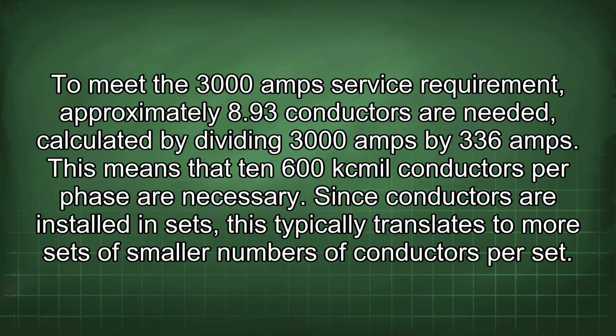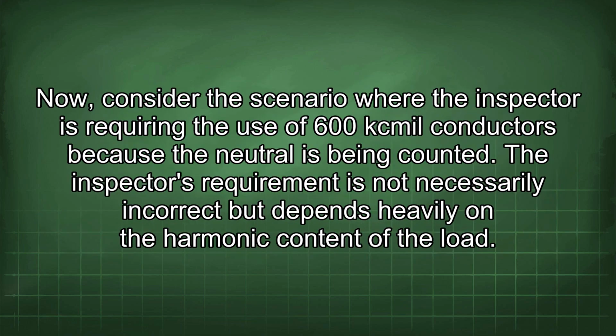Since conductors are installed in sets, this typically translates to more sets of smaller numbers of conductors per set. Now, consider the scenario where the inspector is requiring the use of 600 kcmil conductors because the neutral is being counted. The inspector's requirement is not necessarily incorrect but depends heavily on the harmonic content of the load.